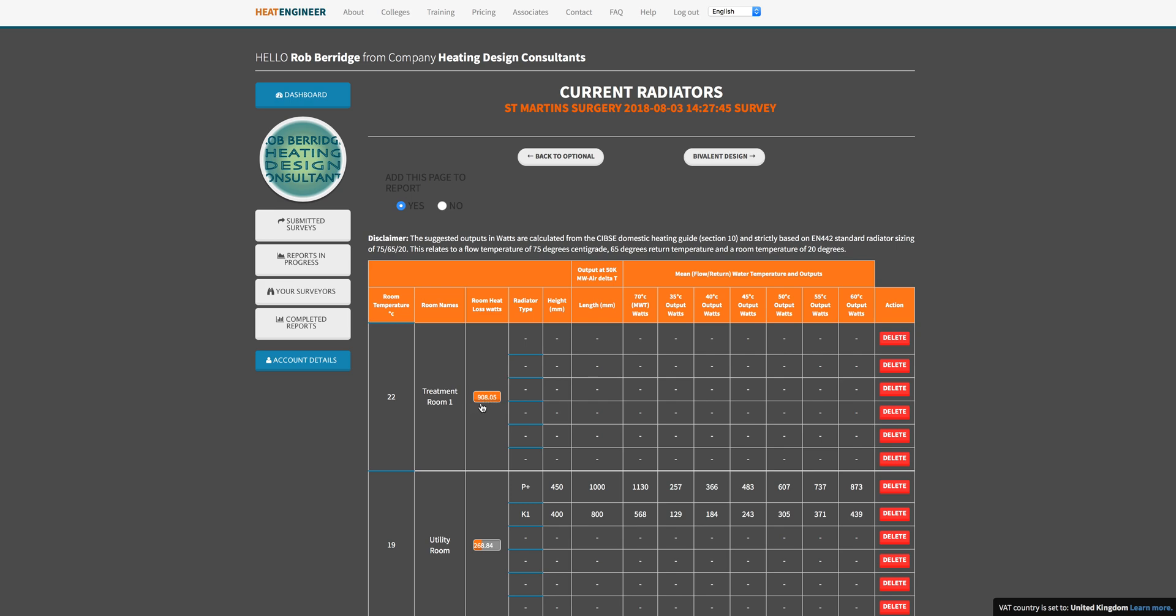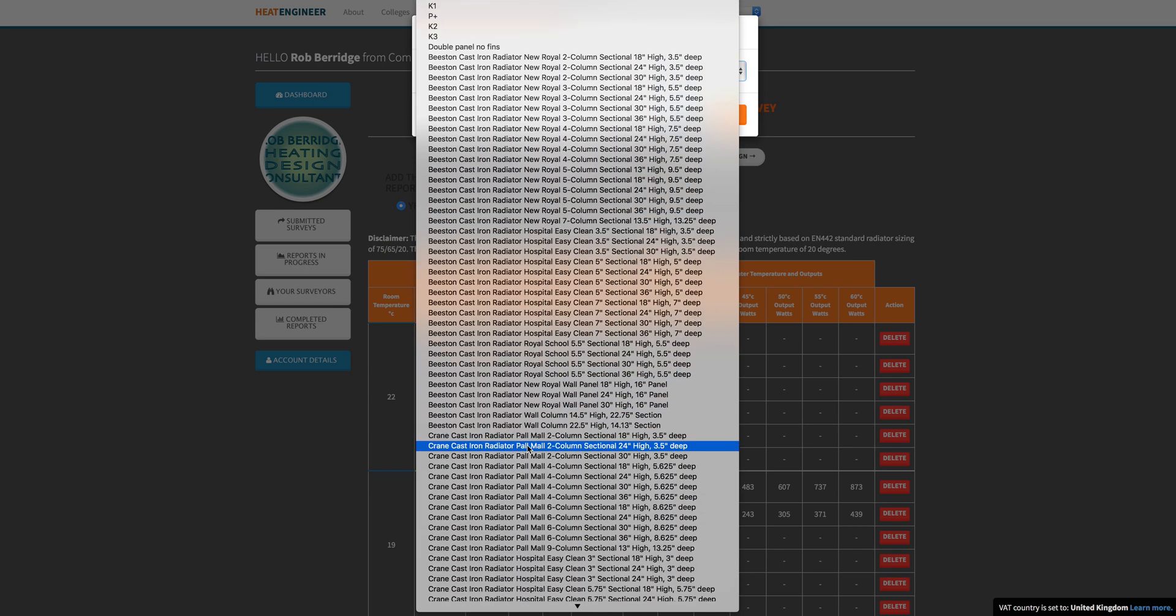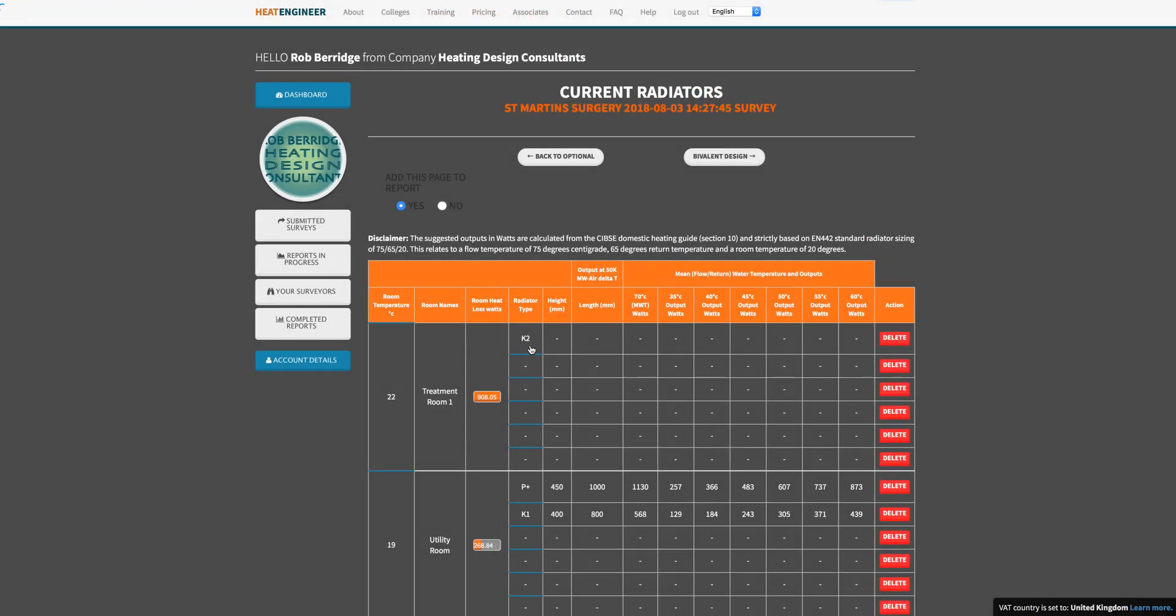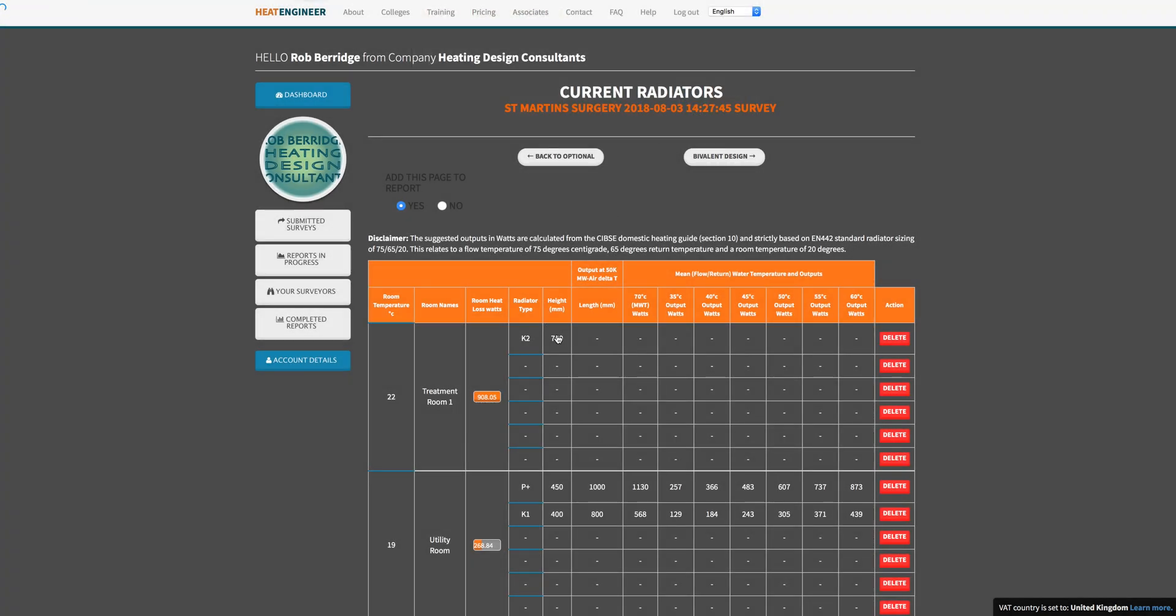If we say we've got a heat requirement of 908 watts here, you can add up to six radiators per room. So if we're installing radiators aesthetically, as opposed to what the output is, we might have a window opening in a bay, and it might be 1300 millimetres long, and we've got room for a 700 mil high radiator. That might be the only position that we've got in the room. So we want to just try and get the biggest radiator we can within that area. If we click on radiator type, and we go into the different types, let's pick a K2 radiator. You can see it starts to populate. If we get our height, let's see if we can get 700 millimetres in there. We said we had 1300 long, so if we allow for some valves, we'll put a radiator in there of 1200 millimetres.